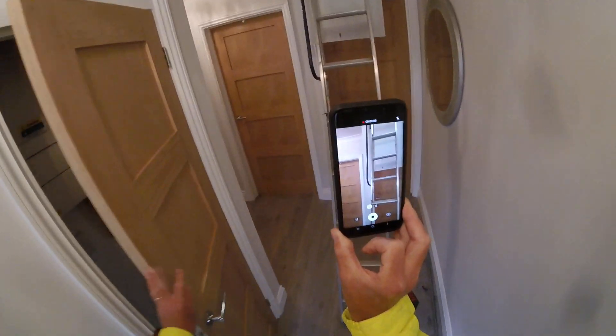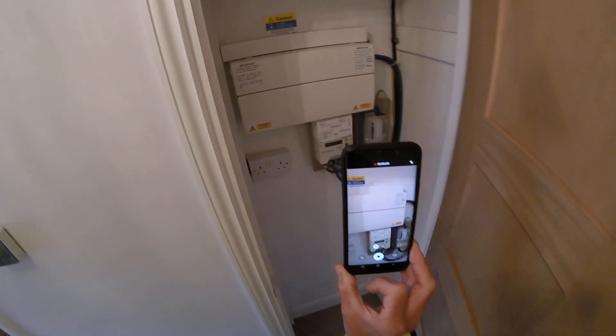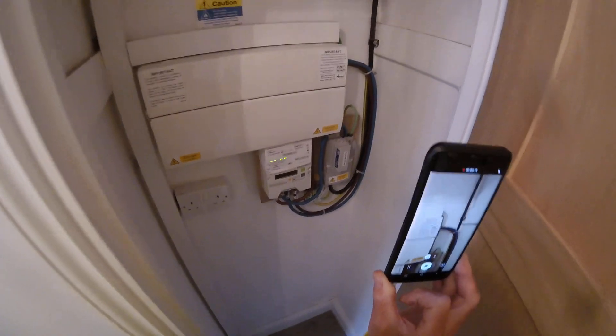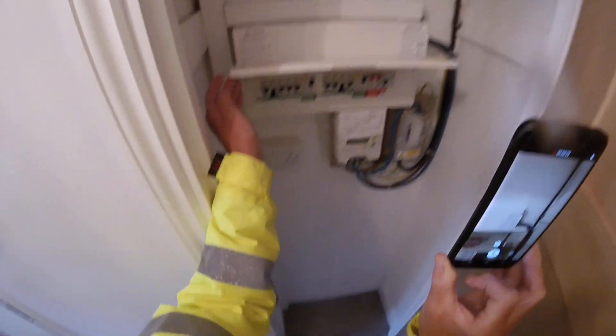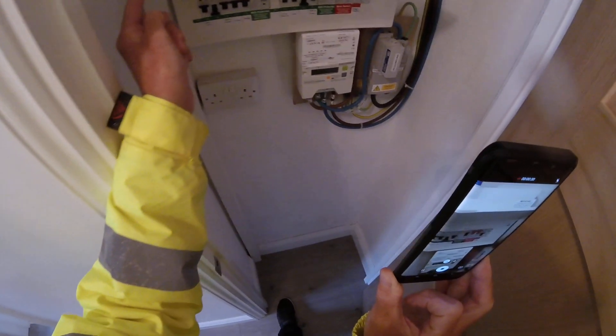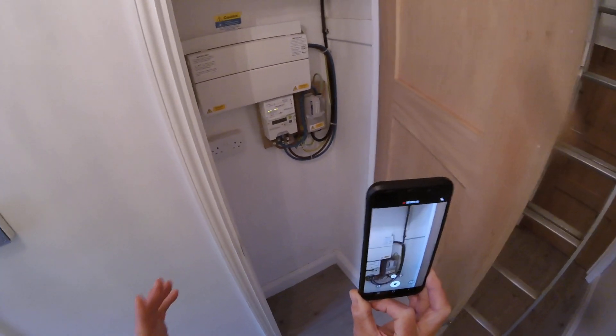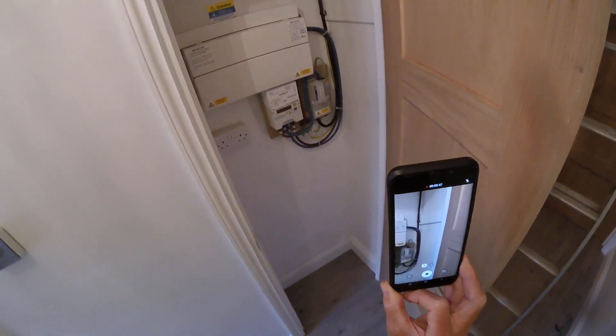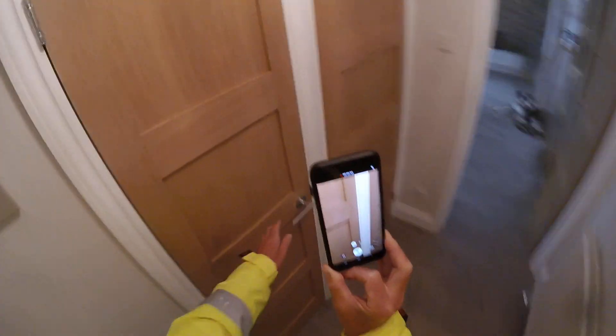This was signed off, so I'm going to cover the electrical side very briefly first. We've got a smart meter installed here and you can see we've got a new consumer unit. This consumer unit is fully compliant with BS 7671 — the wiring regulations. As you can see, all of the residual circuit breakers are installed, you've got two RCD circuits, and also surge protection, so that's right up to the current edition. I won't go too much into compliance documents here — these obviously you'd want to see as evidence either pre or post audit.